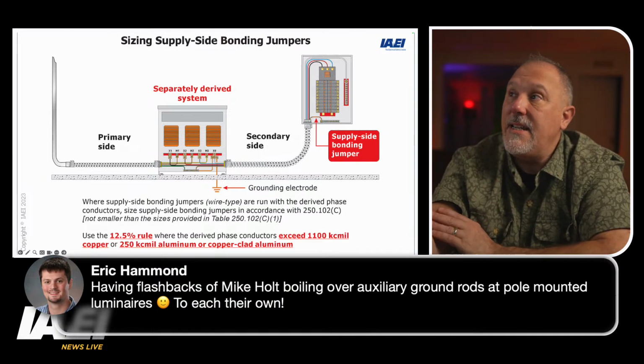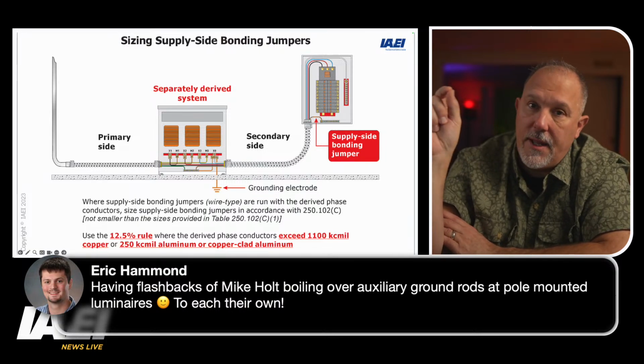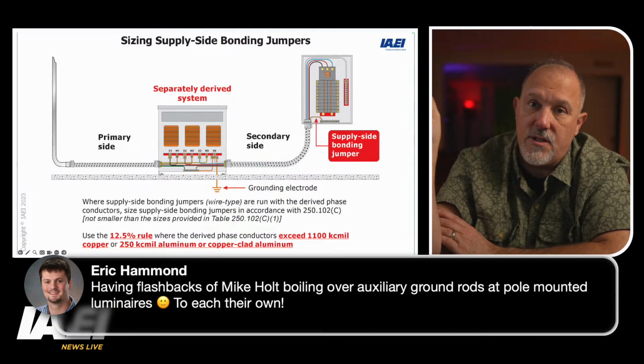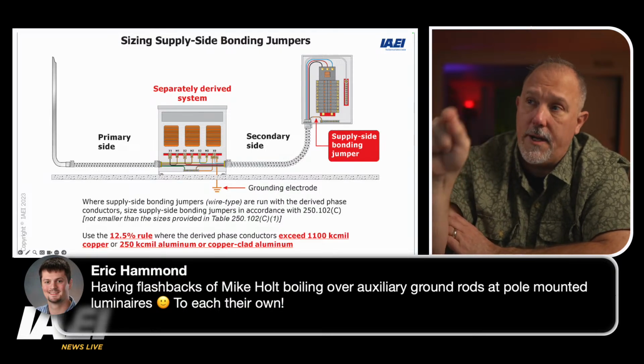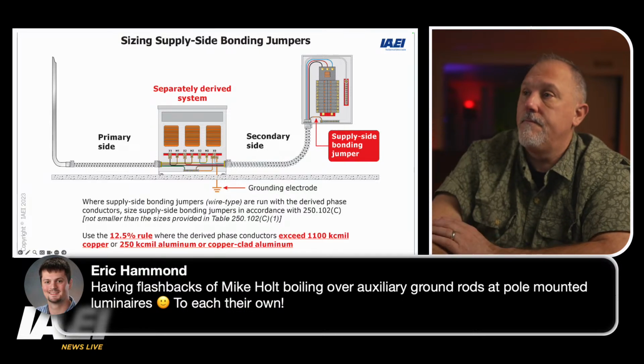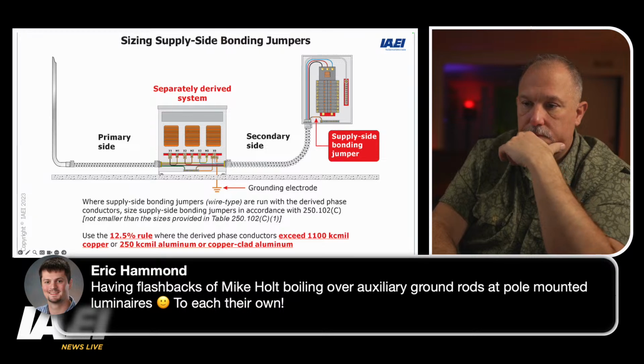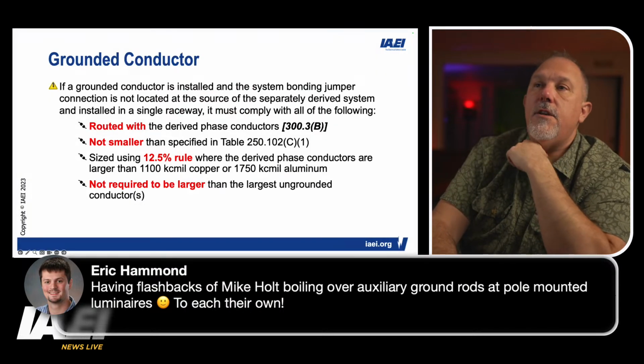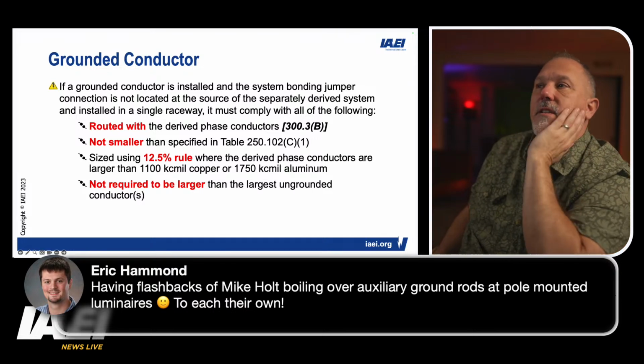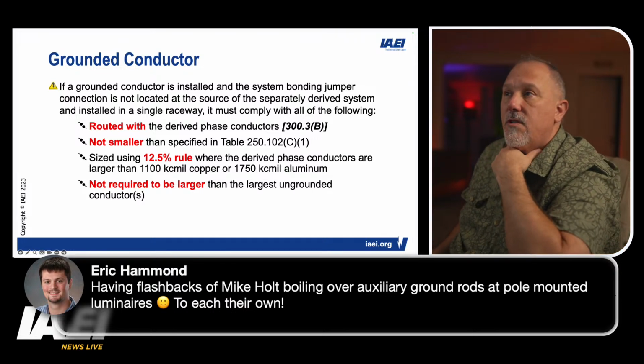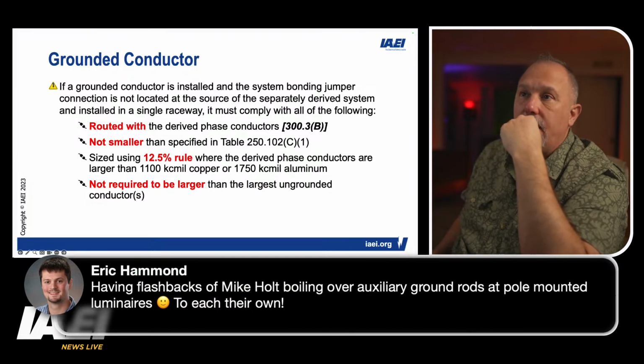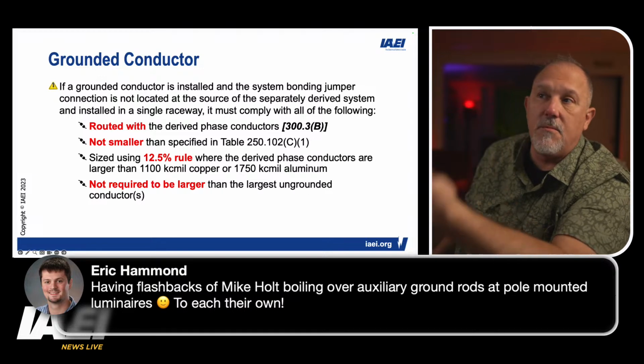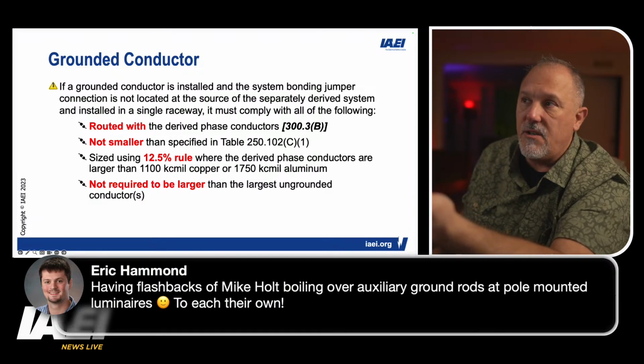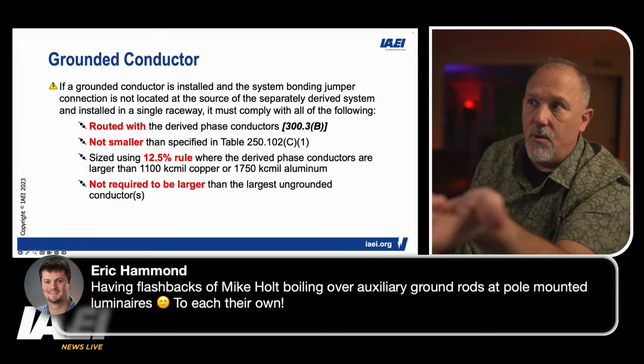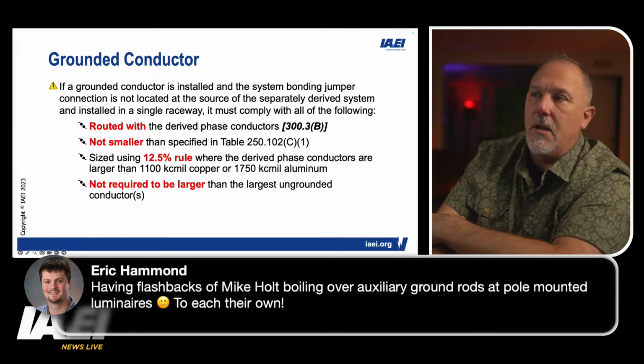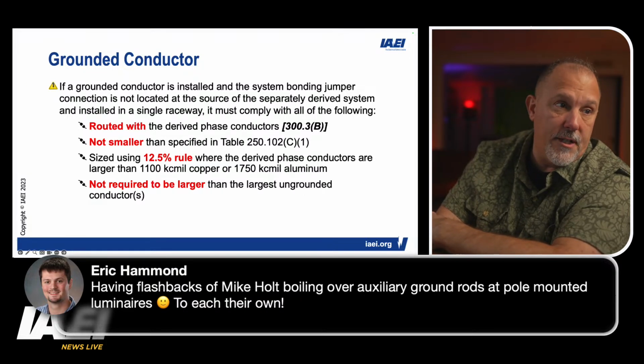And you're going to keep your grounded conductor in that panel separate. You're not going to bond it in that transformer or in that panel board because you've already bonded it in the transformer. Make sense? So if a grounded conductor is installed and the system bonding jumper connection is not located at the source of the separately derived system, installed in a raceway, it has to be routed with the derived phase conductors, not smaller than what's in 250.102(C)(1). You can use the 12.5% rule, and then it's not required to be larger than the largest ungrounded conductors.